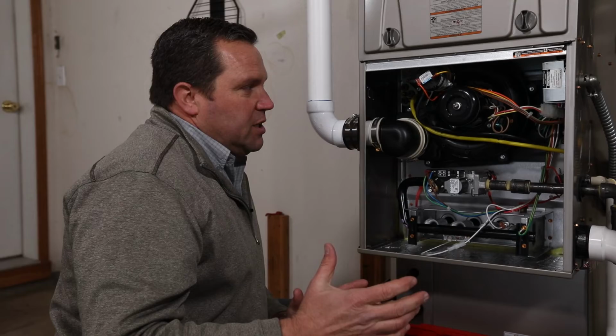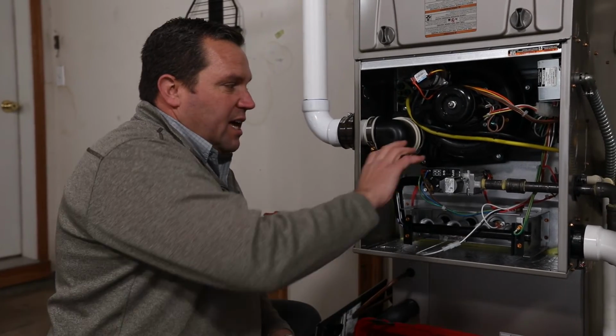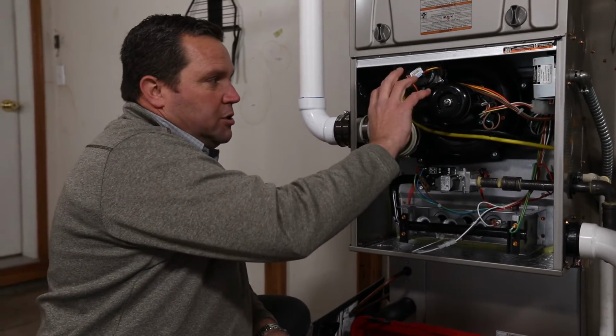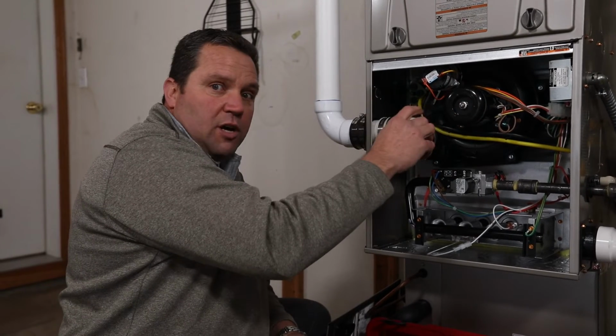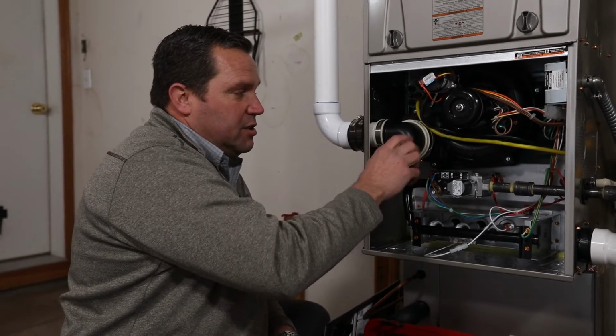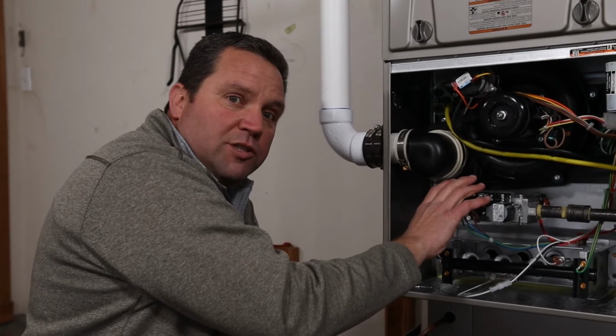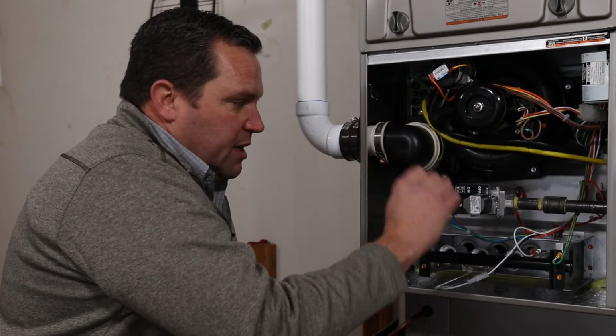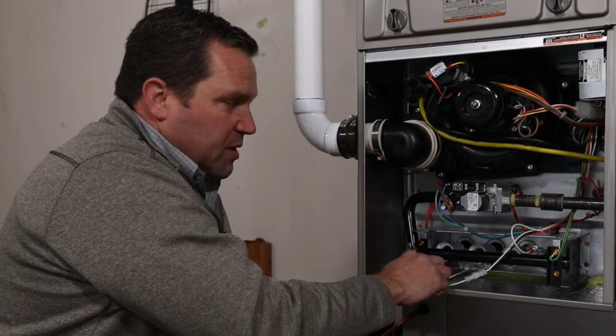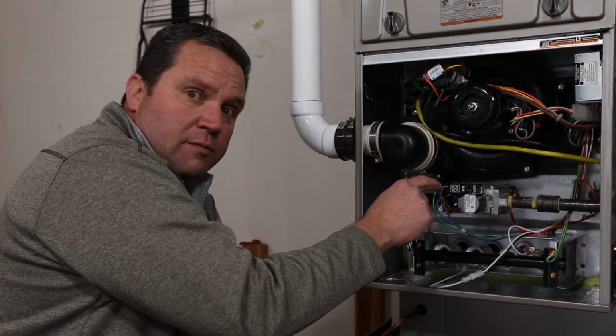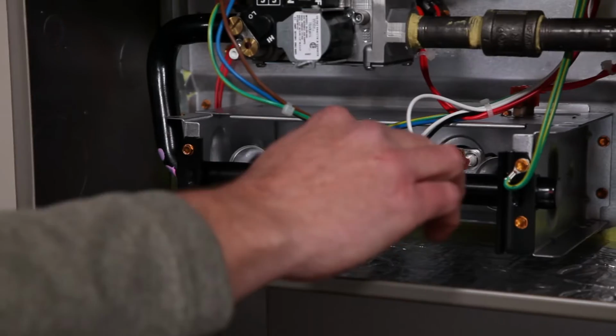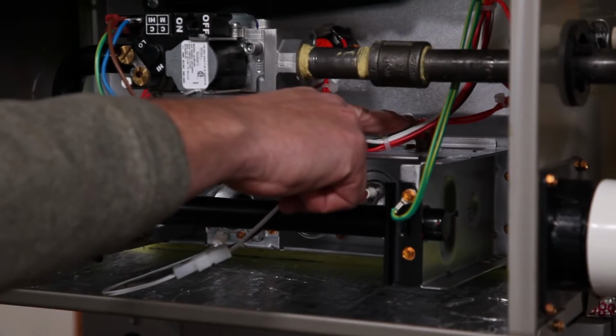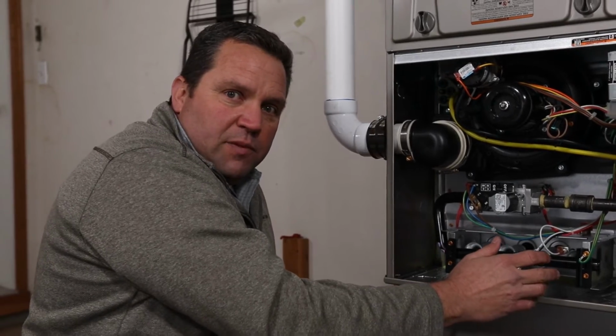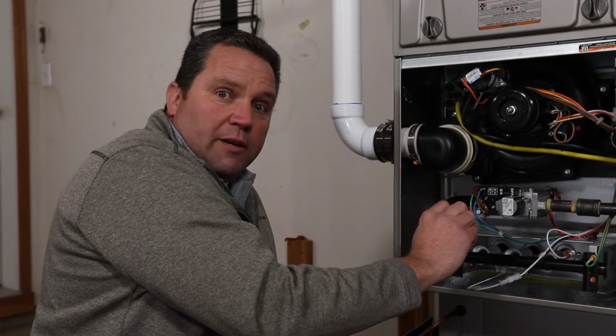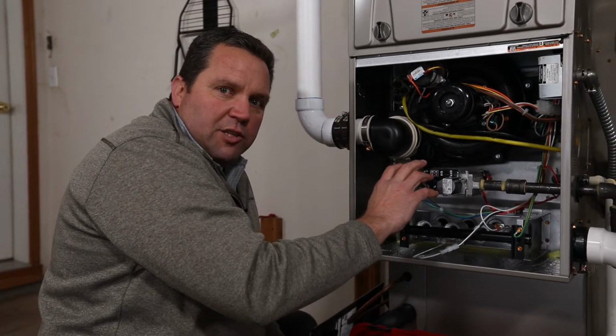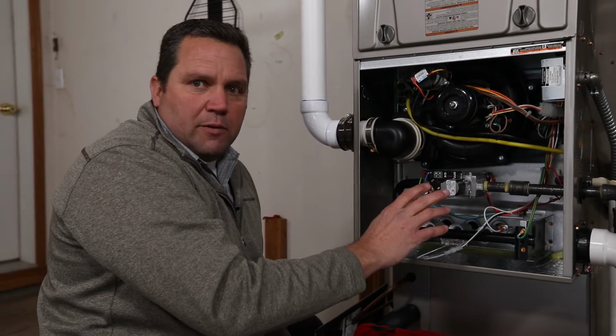So your sequence of operations when a furnace starts is the gas valve is closed, your inducer draft motor turns on, pulls any excess gas that might be in the system out, and that then closes the pressure switches. The igniter will go, the gas valve will open, the flame should start, and then the flame sensor will ensure the flame. If there's not a flame, then the system starts over from the beginning. After 3 tries, the system will shut off because there's a problem.